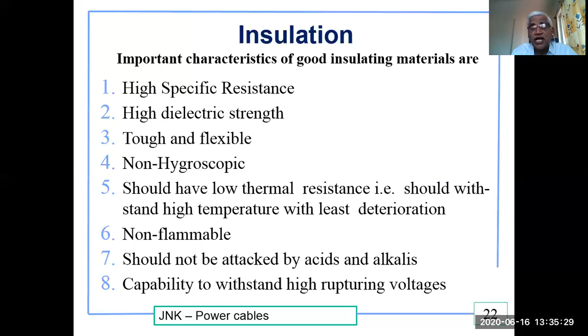Now we know that PVC cable is there, it's called polyvinyl chloride. It is a thermoplastic synthetic compound. It is generally used to insulate the cables. It has a good dielectric strength of the order of 17 kV per millimeter, and maximum continuous temperature is 75 degrees centigrade.